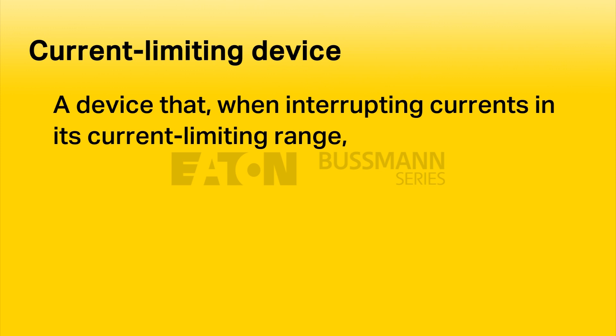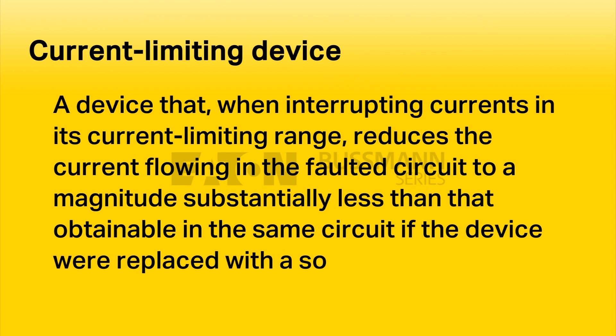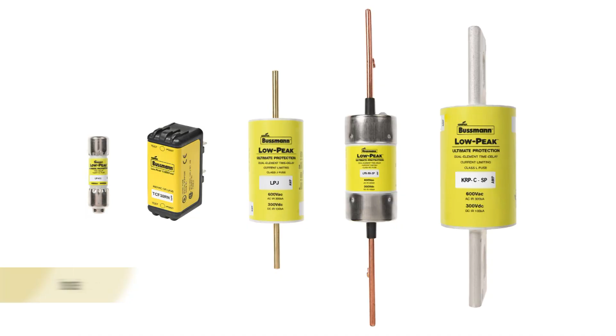Current limitation is a function of how quickly the fuse can react to a fault and clear it before the fault current can build up to destructive levels. NEC 240.2 defines a current limiting device as a device that, when interrupting currents in its current limiting range, reduces the current flowing in the faulted circuit to a magnitude substantially less than that obtainable in the same circuit if the device were replaced with a solid conductor having comparable impedance. Fuses that limit the let-through current to downstream components provide protection from thermal and magnetic forces while providing numerous benefits.